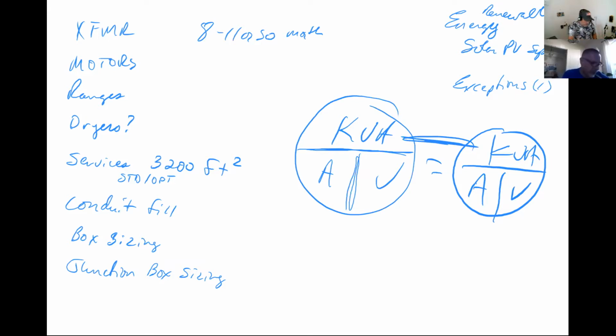So if I had 15 kVA, which would be 15,000 volt amps, the product of amps times volts, which is what the bottom two values are. Let's say it was a 480 volt, 240 volt transformer, and just for simplicity's sake, I know it's not normal, let's call it a single phase for now. So if I were to have a 480 to 240 volt single phase, the math is really simple.